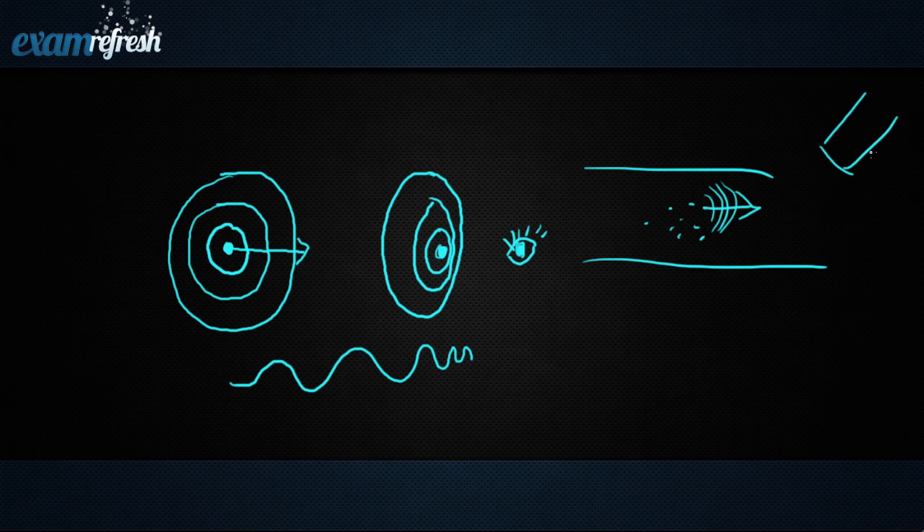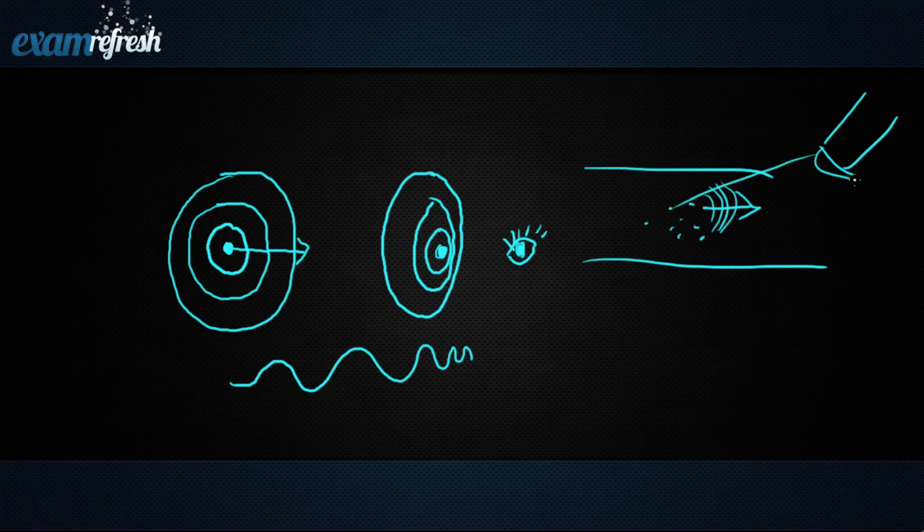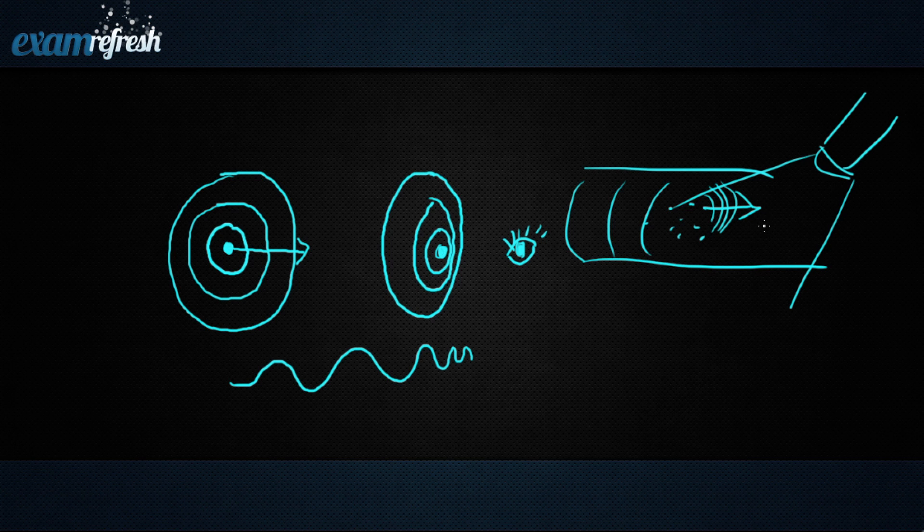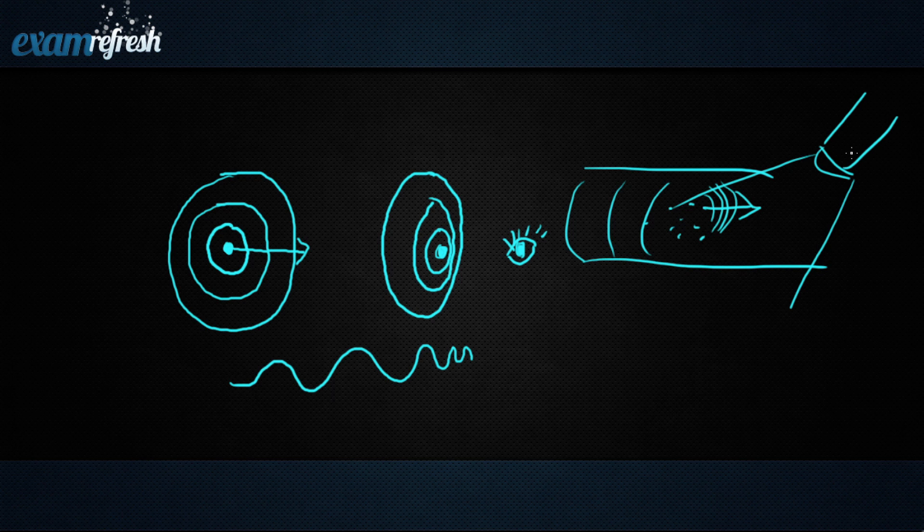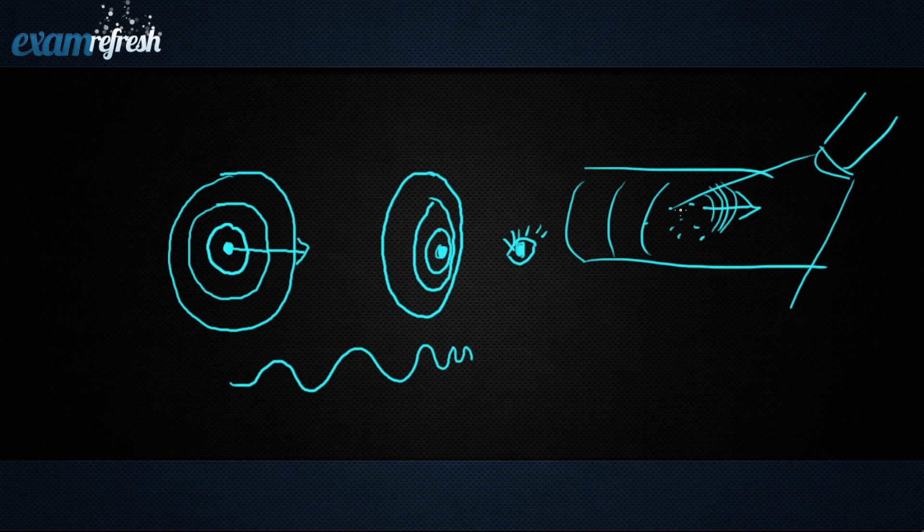And it's going to have a low frequency behind it. So this is how the machine can tell direction of flow. If the high frequency is on this side, it's moving towards the transducer. If the high frequency is on this side, it's moving away.